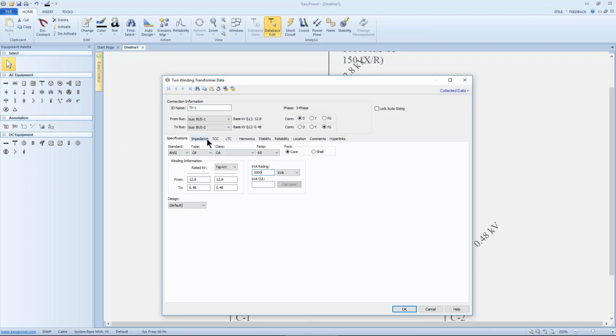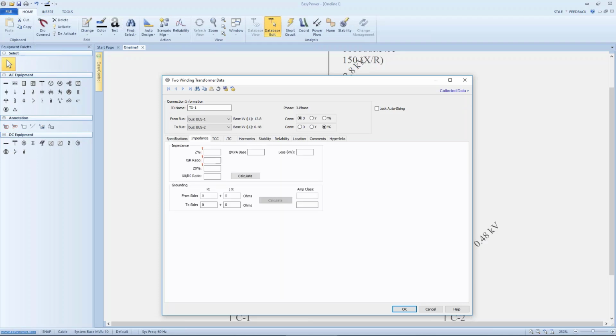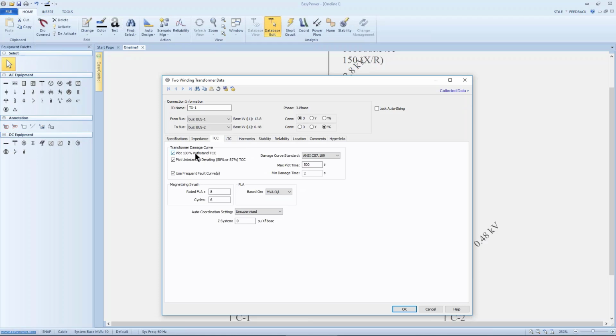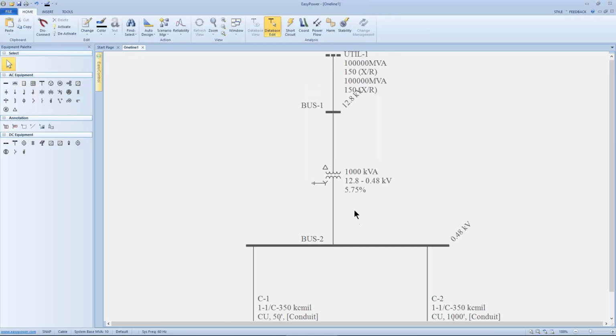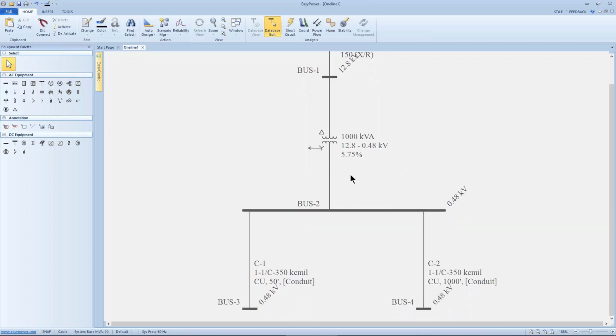Now I'm going to go to the impedance tab. We see more red exclamation points. The impedance on the nameplate says 5.75%. Now, we may not see the X over R ratio or zero sequence ratio on the nameplate, but the tool will calculate those for me. And then when we get to coordination, we'll see the damage curves are plotted by default, these check boxes indicating that. All this is per ANSI standard that's required for an oil-filled transformer.